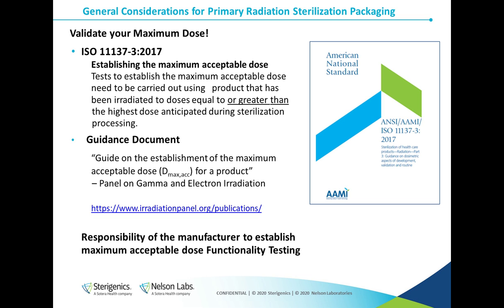One thing that's often overlooked in radiation processing is the validation of the maximum dose, and this applies to both the product and the primary packaging material. There is some guidance in ISO 11137-3 related to this, and there is also some guidance from the panel on gamma and electron irradiation on maximum dose validation, and I've provided a link on this slide to that guidance. Ultimately, it is the responsibility of the manufacturer to validate their maximum dose and ensure both their product and packaging can withstand the maximum dose through functionality testing. And as mentioned before, later on in this webinar, Jennifer Giggy from Nelson Laboratories will review some laboratory testing that is relevant in this area.